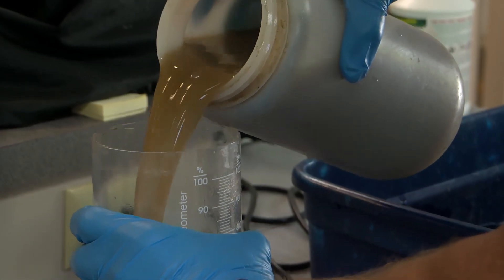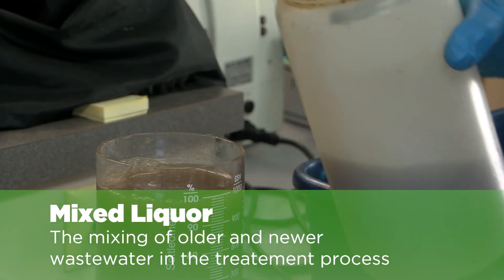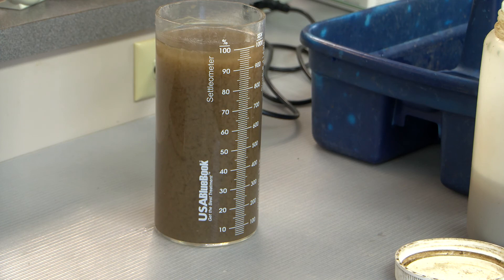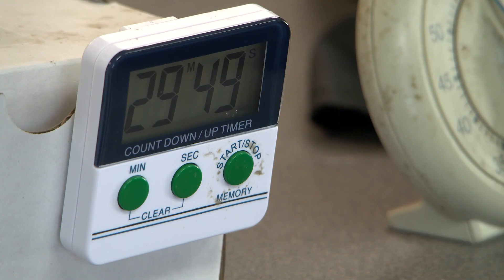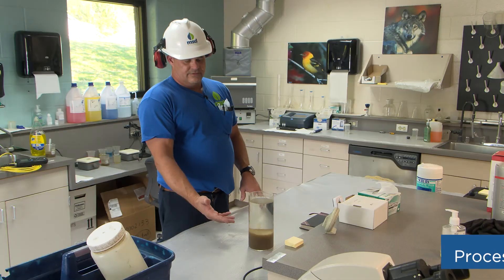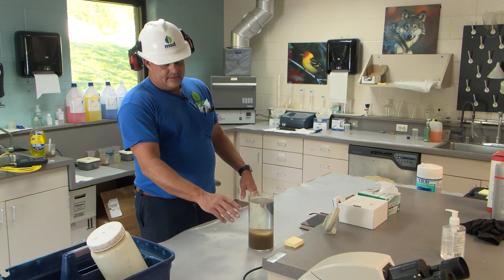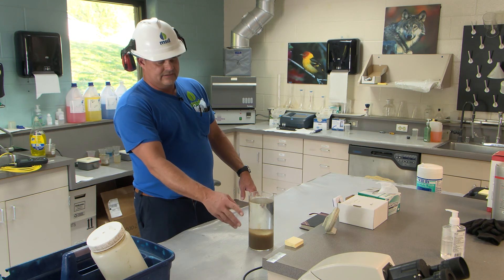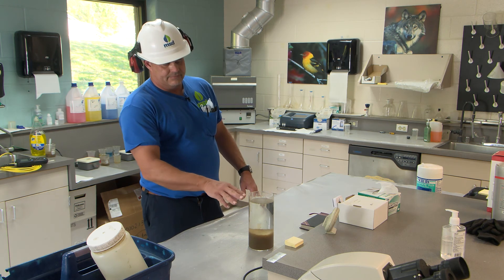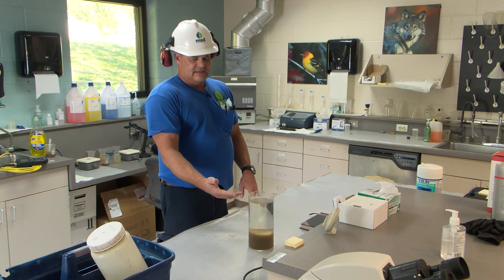The first test we do is a settlometer test — we call it the set test. We grab our mixed liquor from the oxidation ditch and pour it in here. This is a controlled environment so we can see what it's doing inside our clarifiers. In the first five minutes the microorganisms are going to floc together, get dense, and start settling to the bottom, which forces the clear water up through the top and filters it as it goes. If this happens too quickly it won't catch all the particles and the water will get discolored. If it happens too slowly, you'll get some scum floating on top. That tells the operator what adjustments need to be made.